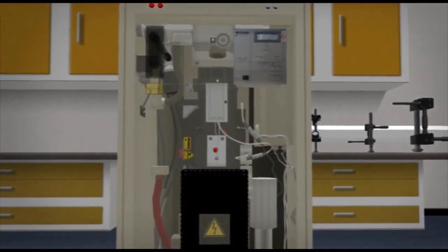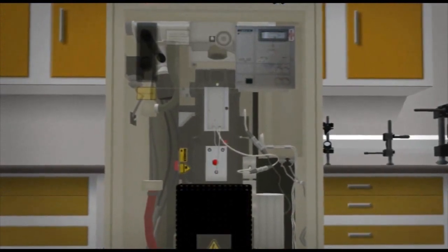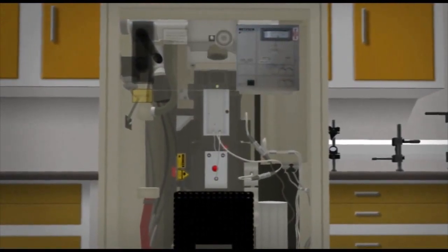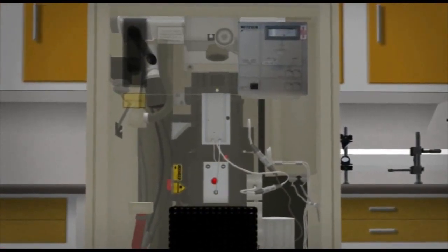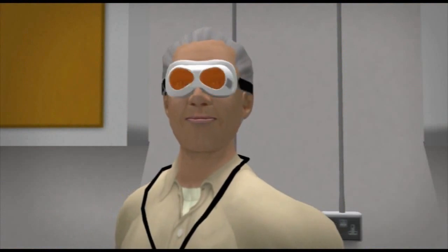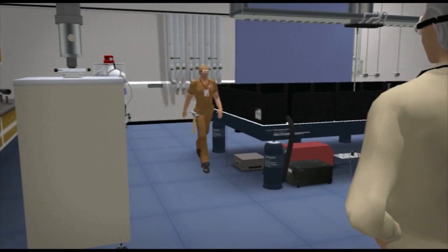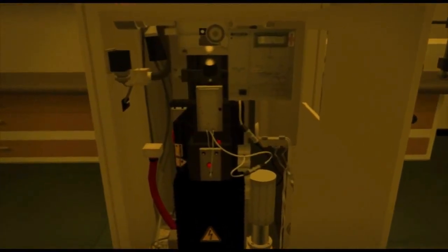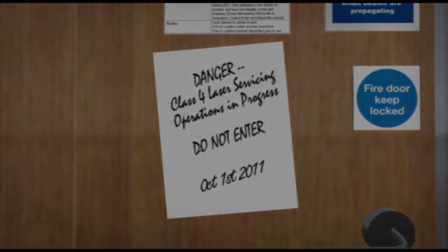This significantly reduces the potential hazard they pose and means that the unit can be reclassified as an embedded laser. Embedded lasers are usually considered equivalent to Class 1 lasers, as they pose no greater hazard during normal operation. It is important to keep this in mind when users or service engineers are required to defeat the control measures for servicing or to sustain normal operations. By opening the enclosure, you may be exposing yourself to the much greater hazard of a higher class of laser.